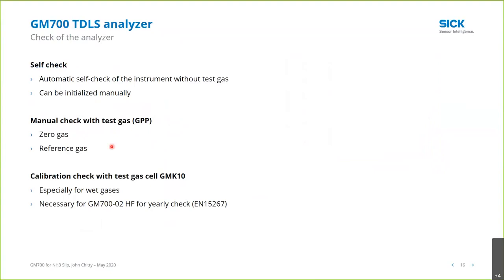We can also, with the GPP probe, which we'll take a look at next, and only with the GPP probe, actually do a zero and span check in place with cal gas. And then we have the GMK10 external cell. We can remove the analyzer head from the probe and attach an external cell and do a check with cal gases. This is something you might do on an annual basis. It depends on your permit, and you can equate that to doing a CGA, a cylinder gas audit on a CEMS analyzer. It's kind of the same thing.